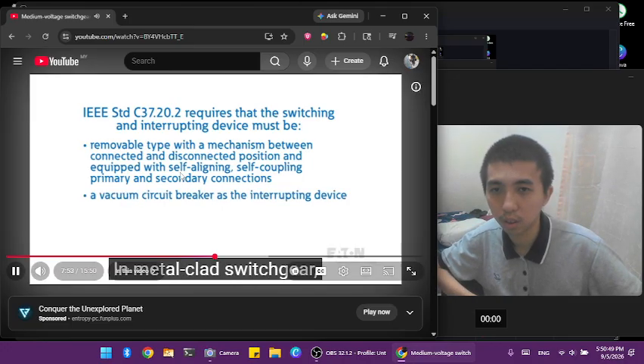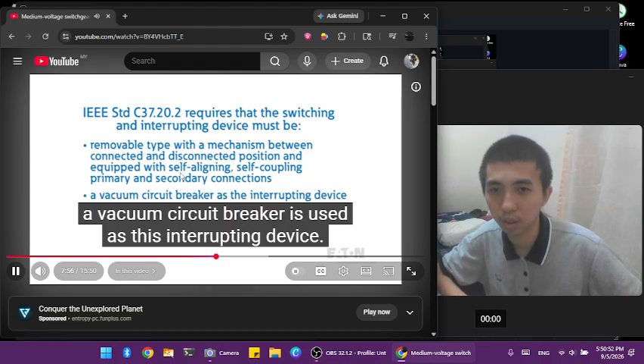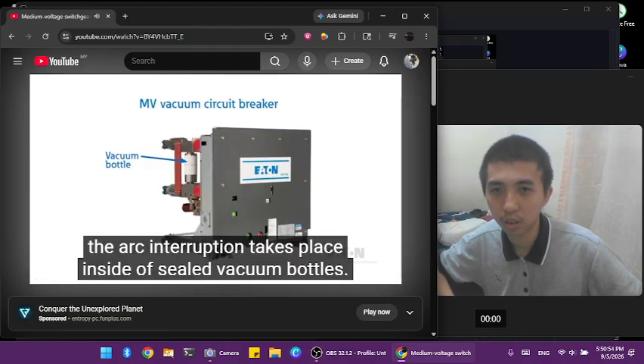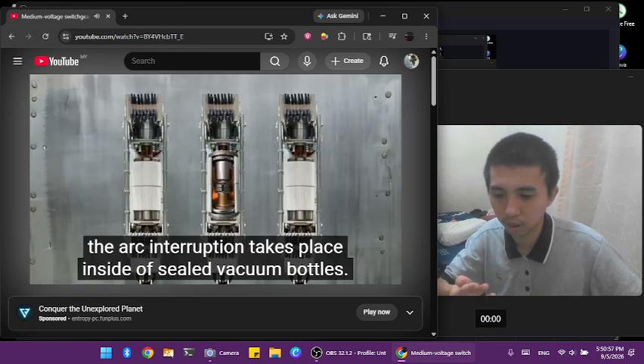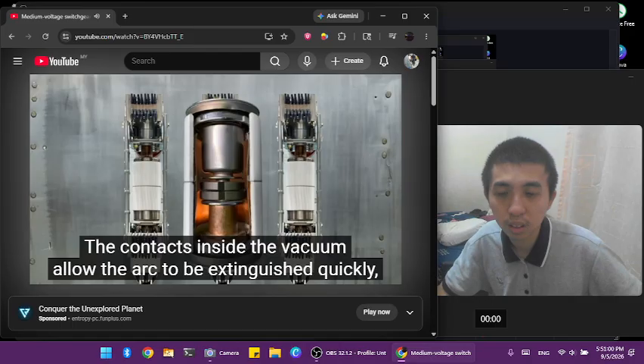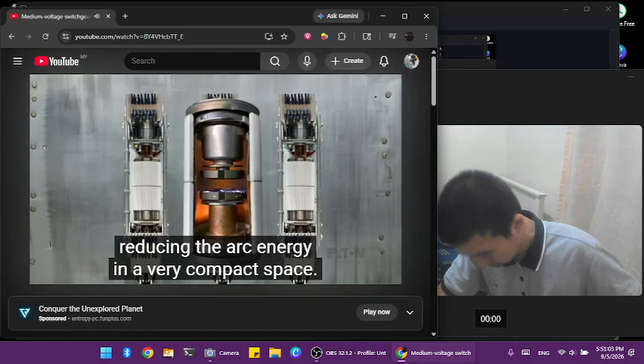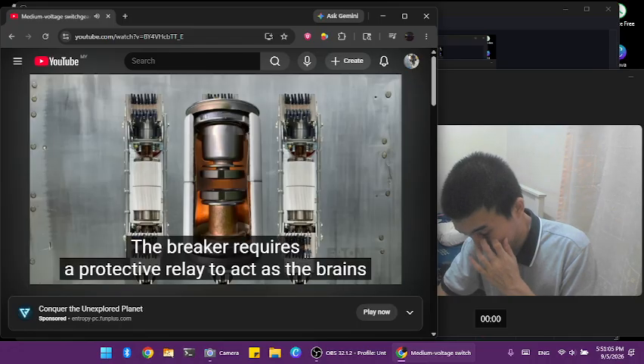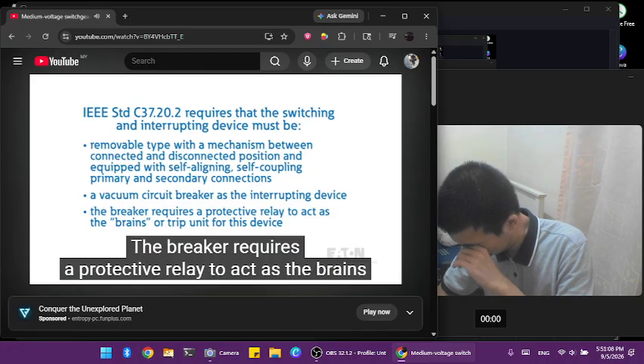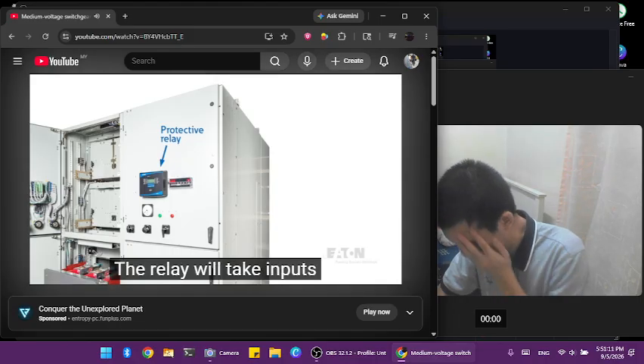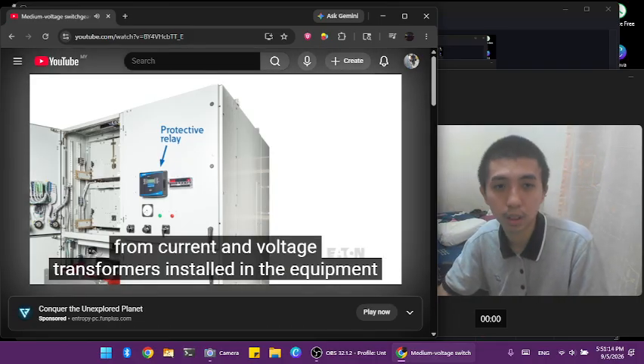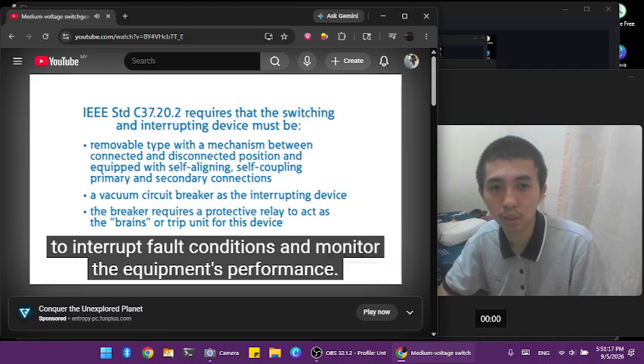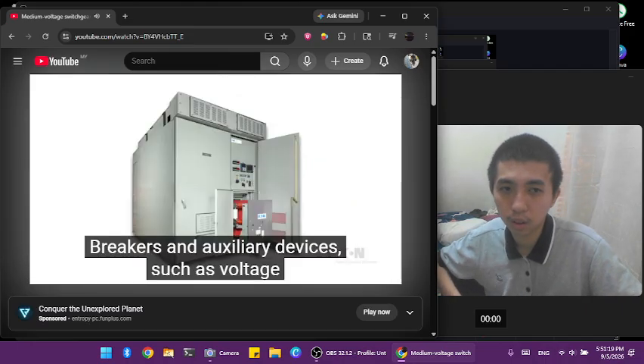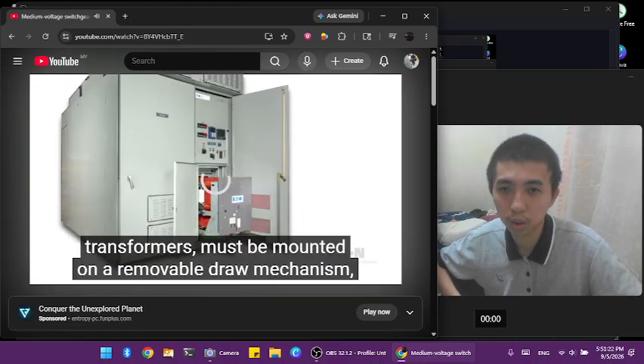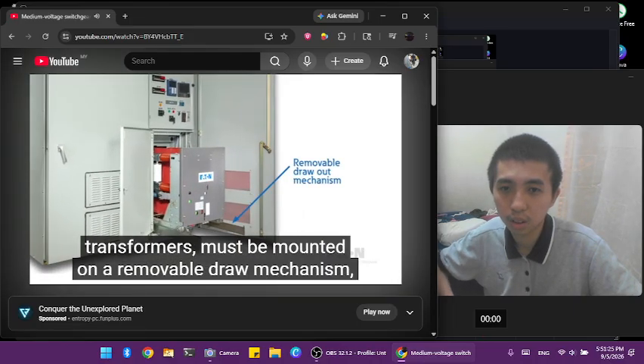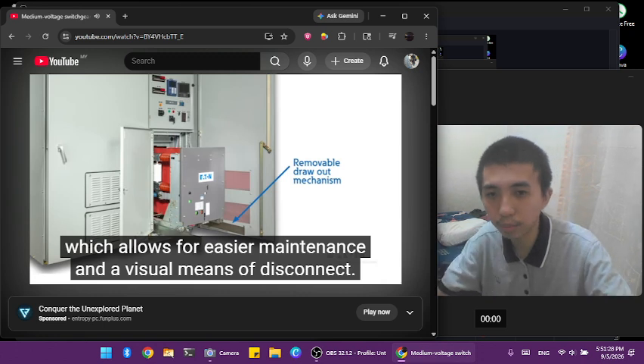In metal-clad switchgear, a vacuum circuit breaker is used as this interrupting device. In a vacuum circuit breaker, the arc interruption takes place inside of sealed vacuum bottles. The contacts inside the vacuum allow the arc to be extinguished quickly, reducing the arc energy in a very compact space. The breaker requires a protective relay to act as the brains or trip unit for this device. The relay will take inputs from current and voltage transformers installed in the equipment to interrupt fault conditions and monitor the equipment's performance. Breakers and auxiliary devices such as voltage transformers must be mounted on a removable draw-out mechanism, which allows for easier maintenance and a visual means of disconnect.